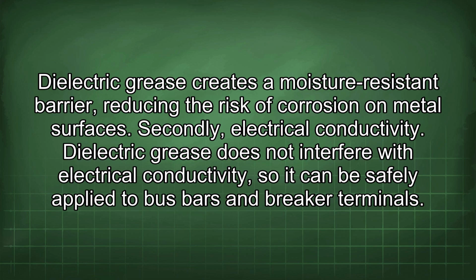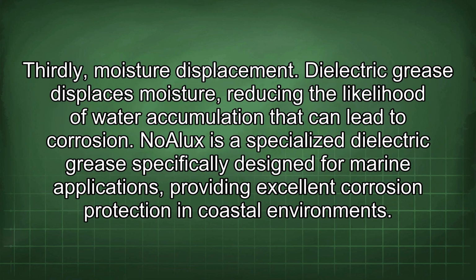Secondly, electrical conductivity. Dielectric grease does not interfere with electrical conductivity, so it can be safely applied to bus bars and breaker terminals. Thirdly, moisture displacement. Dielectric grease displaces moisture, reducing the likelihood of water accumulation that can lead to corrosion.